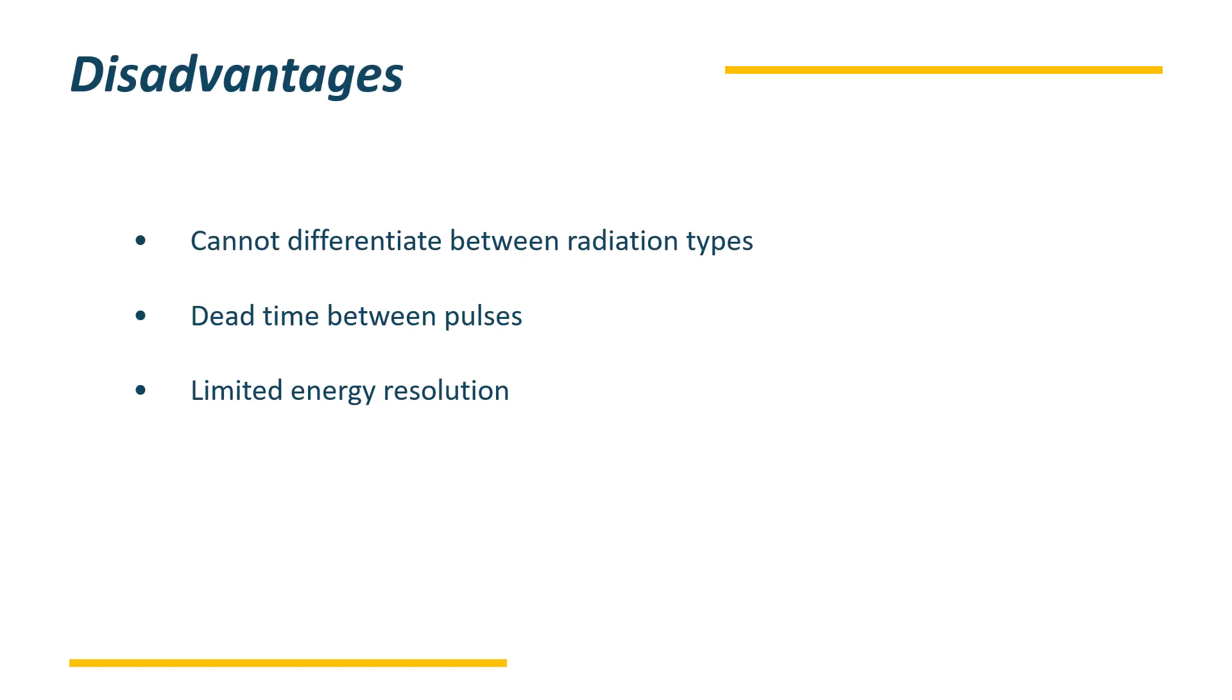At the same time, it is having certain kinds of disadvantages. There will not be much amount of discrimination in between the radiation types. Dead time will be seen in between the two pulses. And energy resolution is limited in case of GM counter.